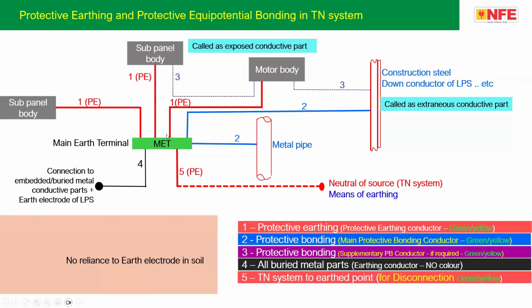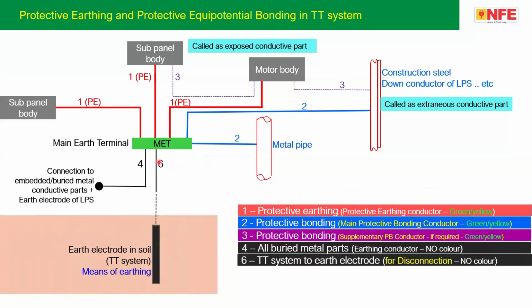And the MET has to be connected back to the neutral of the source, which is called the means of earthing. So here, I'm just writing: the MET is connected to the neutral of the source. This is for a TN system. In the case of a TT system, the MET is connected to the earth electrode in soil. However, TT systems are legally not recognized in the regulation because the regulation always says there should be an earth terminal, meaning a TN system.